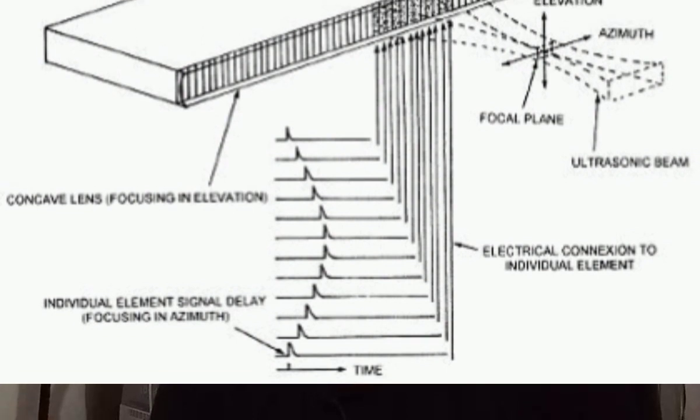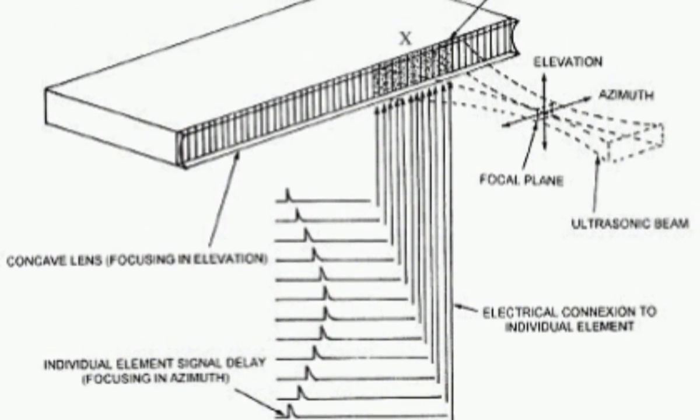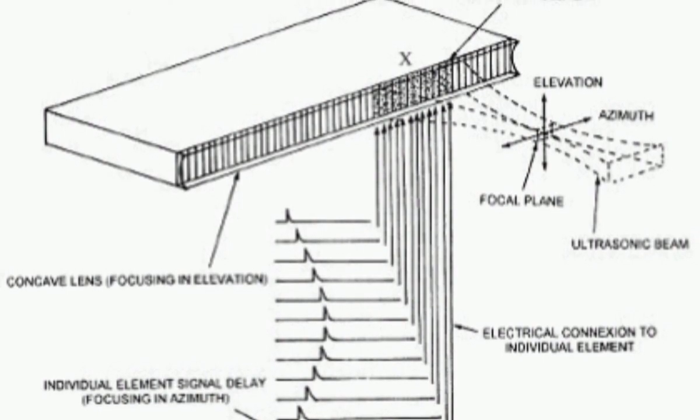Array transducers — almost all modern transducers are electronic arrays. An array is the collection of active elements or crystals within a single transducer assembly. Each active element is connected to its own electric circuitry and is isolated from its neighboring crystal, both electronically and acoustically. The active elements in the array can be fired individually or together to form the beam.